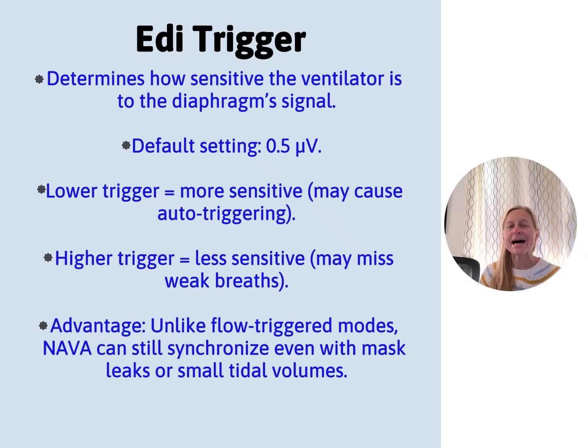So when your trigger is high and it's less sensitive, that baby takes like a little breath. The vent doesn't realize it, so it's not pushing out the support, right? So then you have these unsupported breaths, and we don't want the babies to have too many of that. So unlike flow triggered modes, NAVA can still synchronize when there's a leak or really small tidal volumes, which is really, really helpful, as we all know.